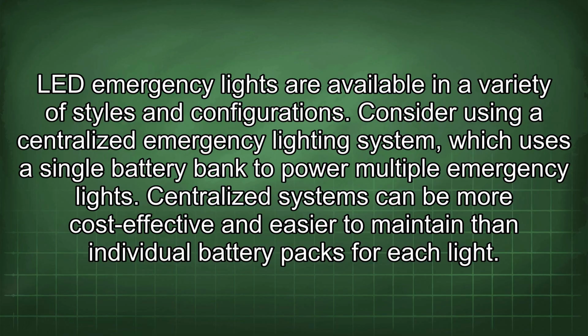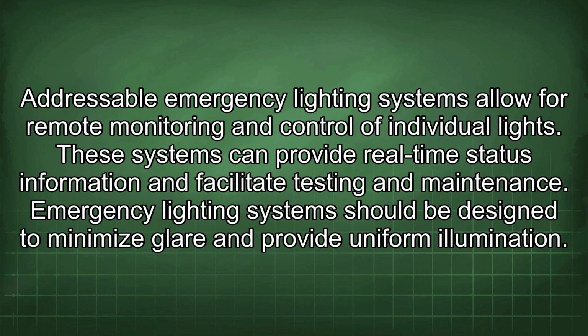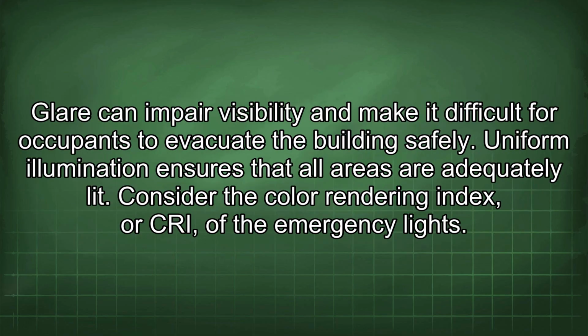Consider using a centralized emergency lighting system, which uses a single battery bank to power multiple emergency lights. Centralized systems can be more cost-effective and easier to maintain than individual battery packs for each light. Addressable emergency lighting systems allow for remote monitoring and control of individual lights. These systems can provide real-time status information and facilitate testing and maintenance. Emergency lighting systems should be designed to minimize glare and provide uniform illumination. Glare can impair visibility and make it difficult for occupants to evacuate the building safely. Uniform illumination ensures that all areas are adequately lit.